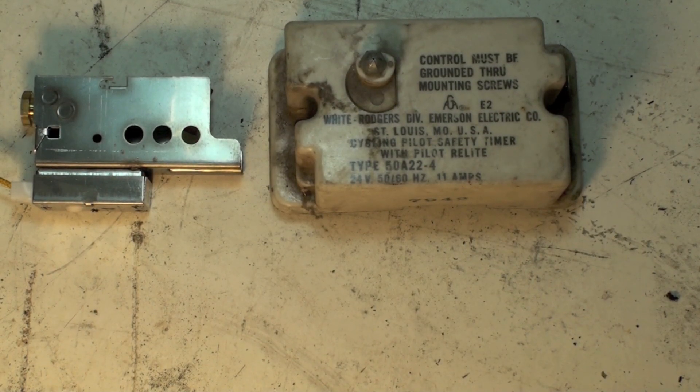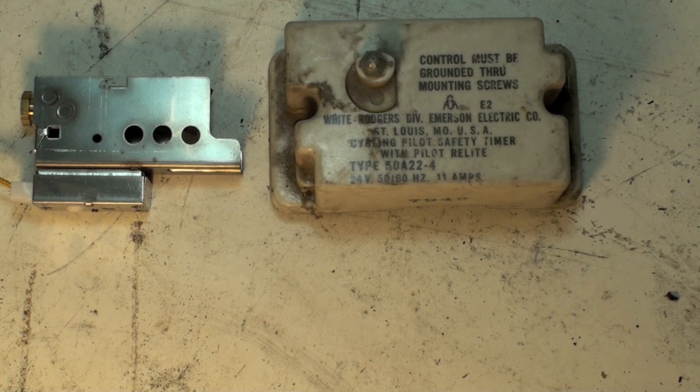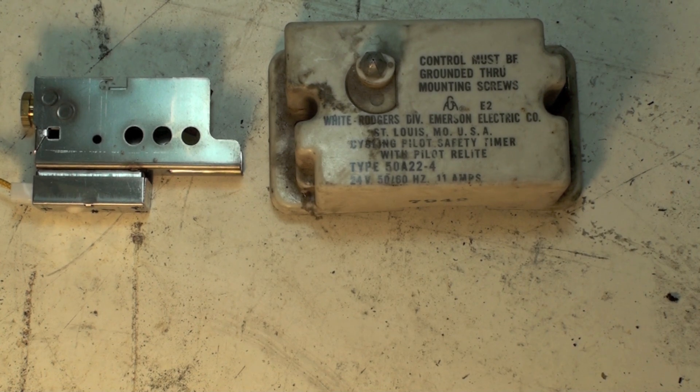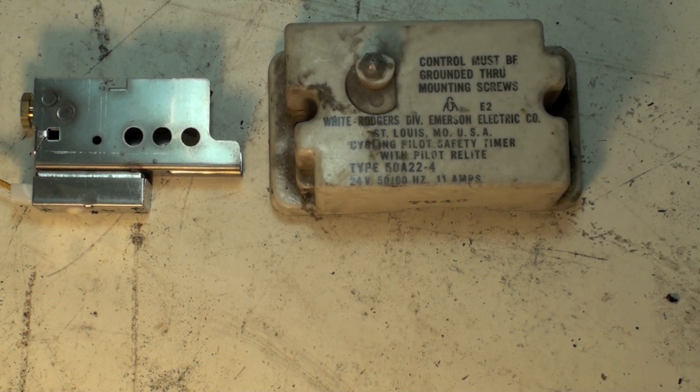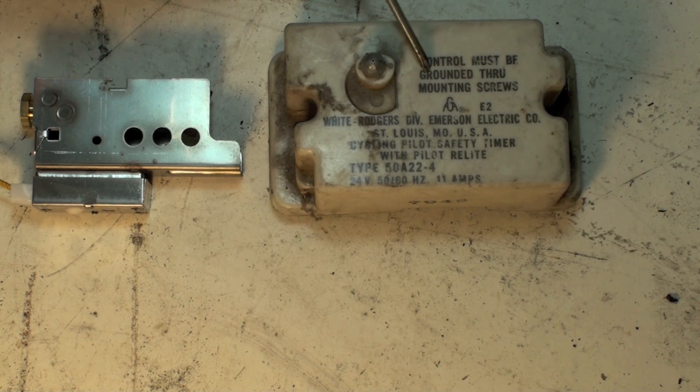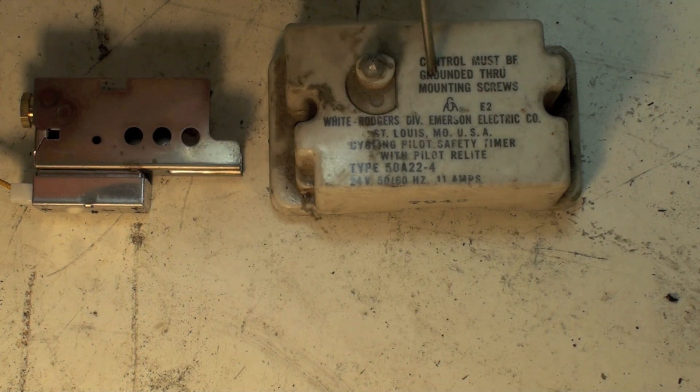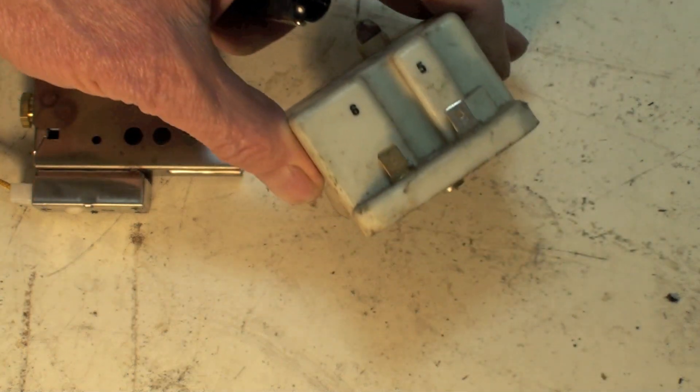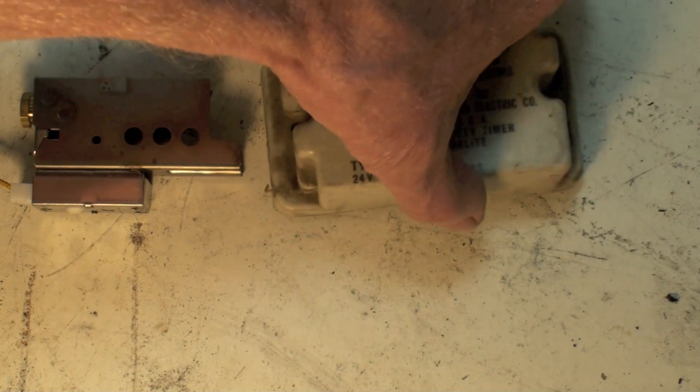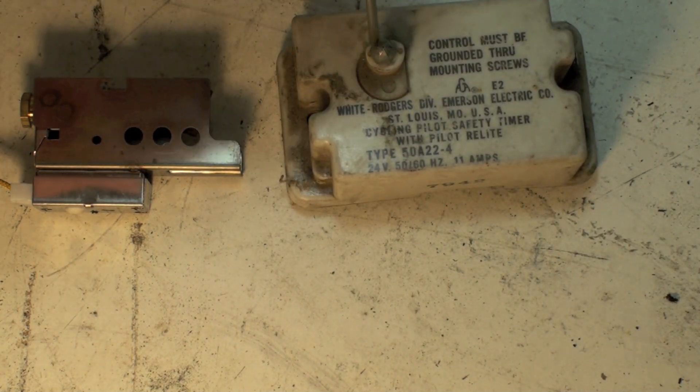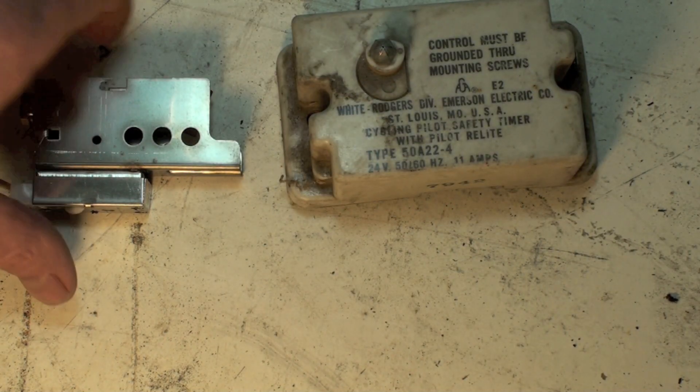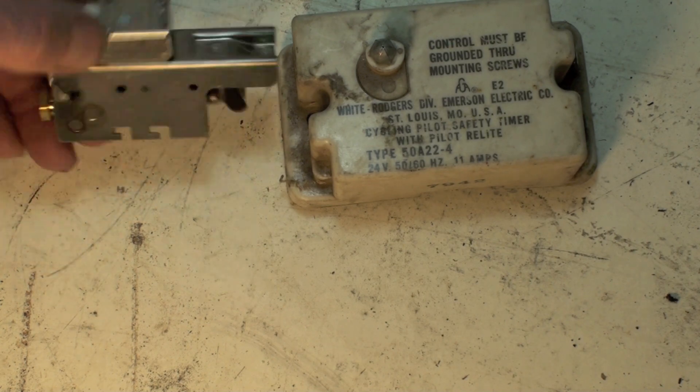This is one of the early forms of a pilot relight system in case the pilot went out. This is a spark coil. Power is fed in through these two terminals and it's raised up to eight or ten thousand volts, comes out of here and sparks across a gap in this pilot assembly.